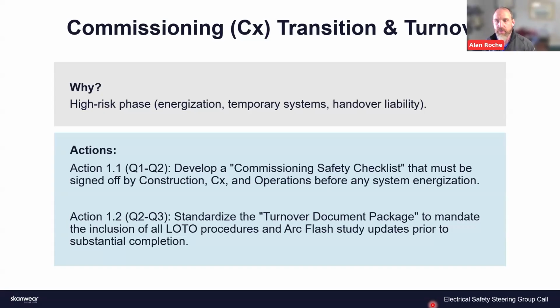Temporary systems all play a crucial role into getting buildings across the finish line. Things to consider are temporary power feeds, any kind of jumper or bypass, temporary cooling or temp water systems to support the testing, any temporary alarm monitoring while we're doing this, partial control sequences, control modifications. These temporary systems are typically less redundant, more manually controlled, manually operated, with a higher dependency on human beings to be operating them.